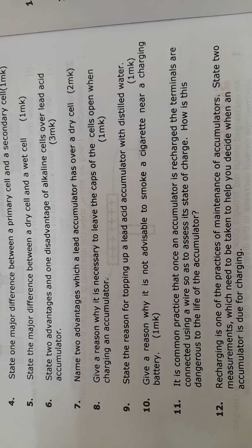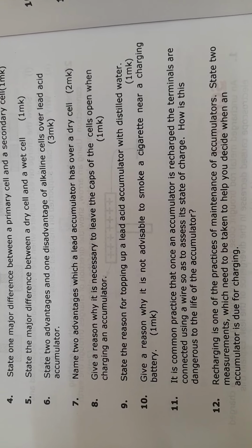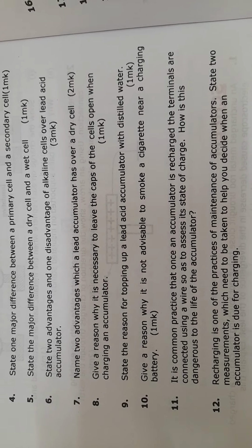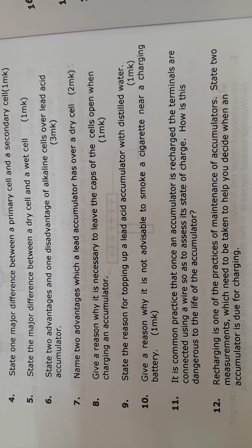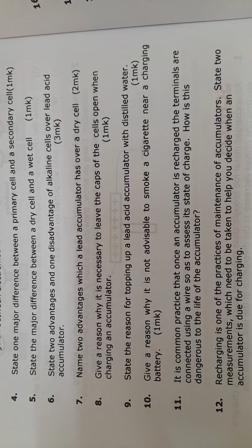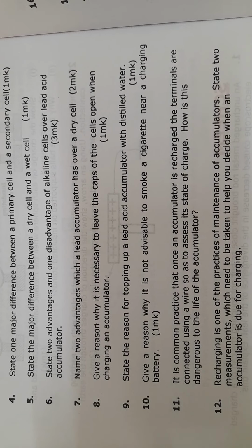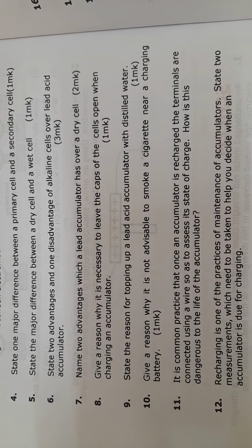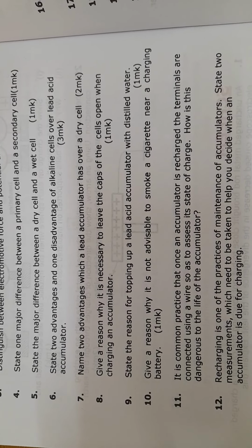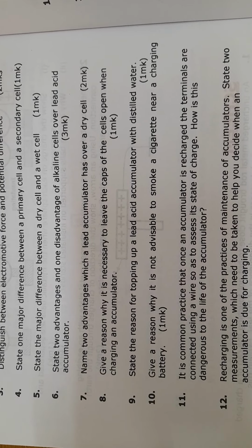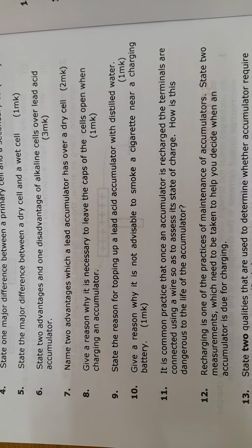It is because when charging an accumulator, there is production of hydrogen gas that needs to escape. So if you don't leave the caps open, the cell will burst. To avoid that, we leave the caps open so that any hydrogen produced can escape out of the cell.